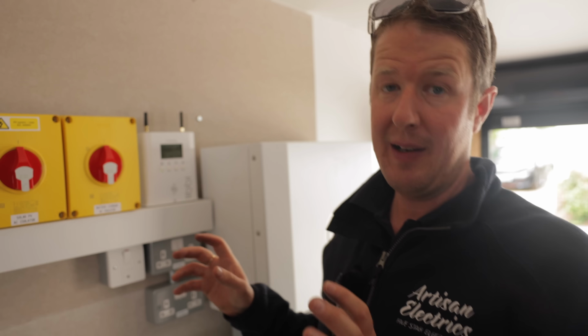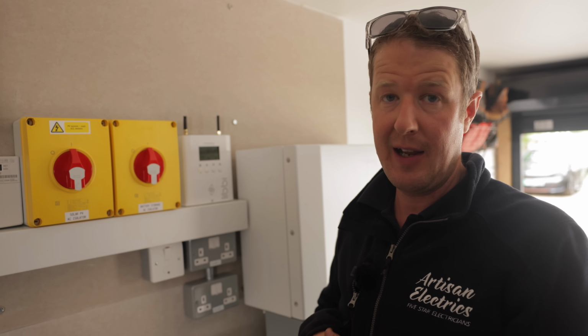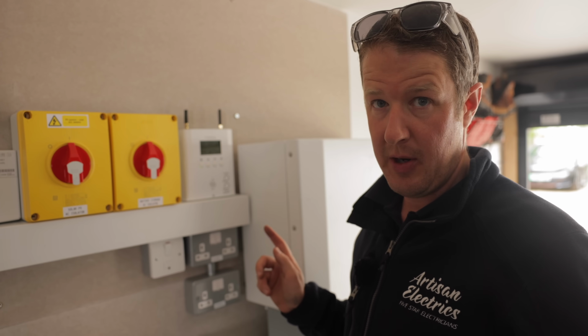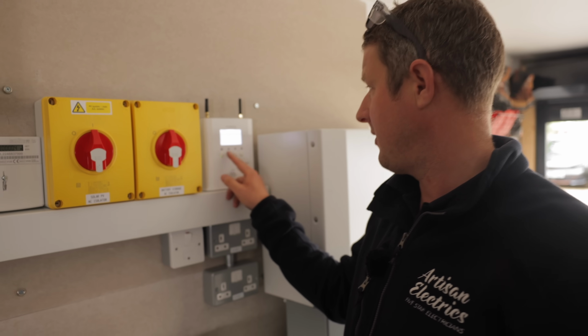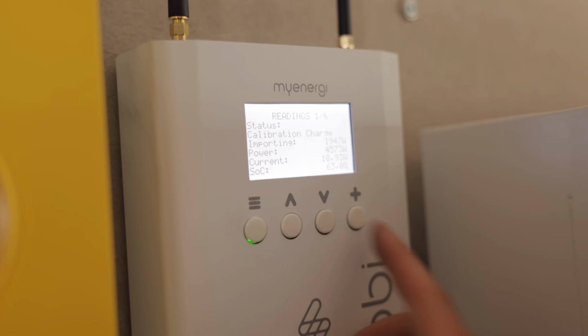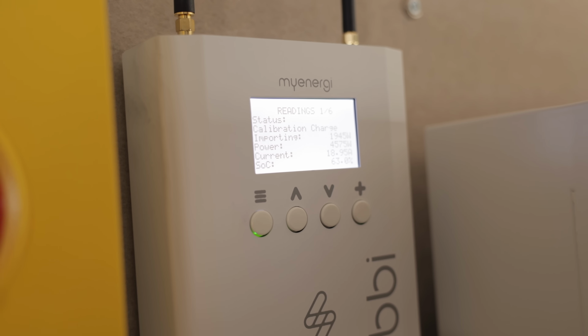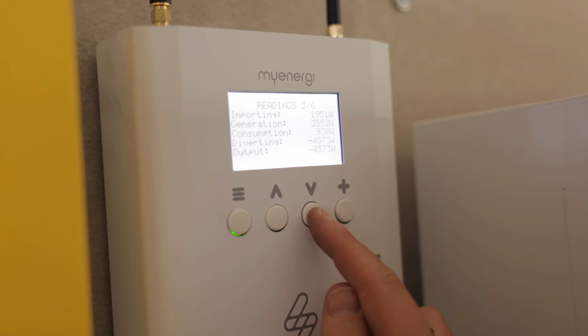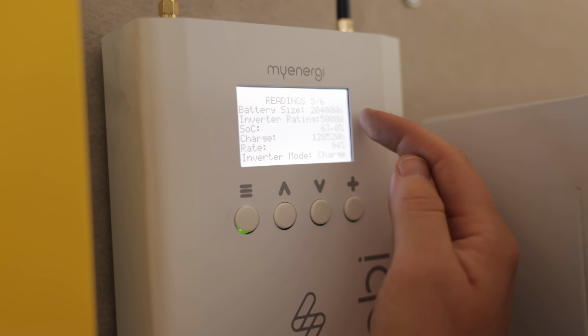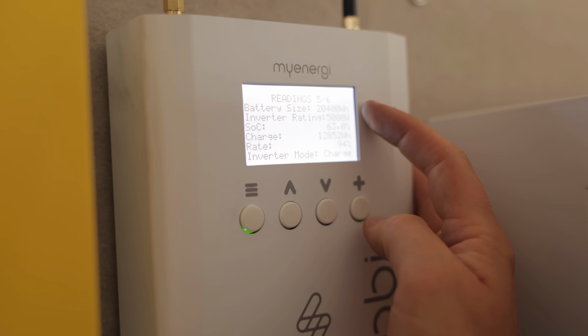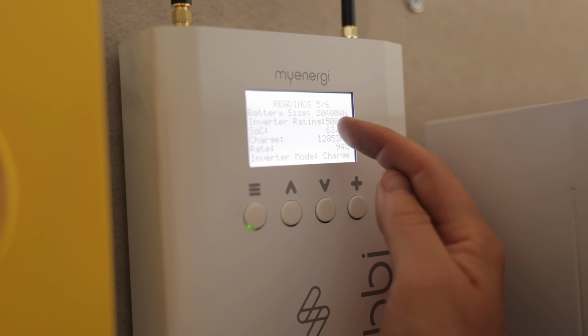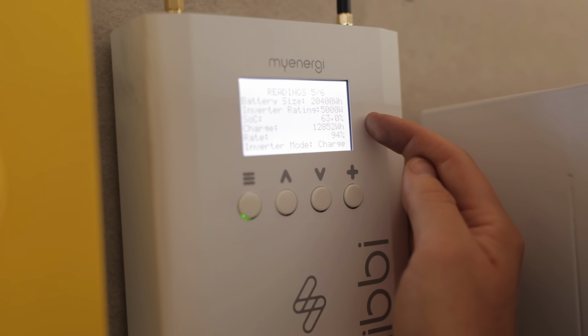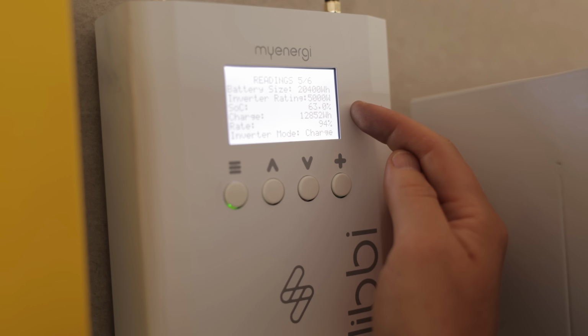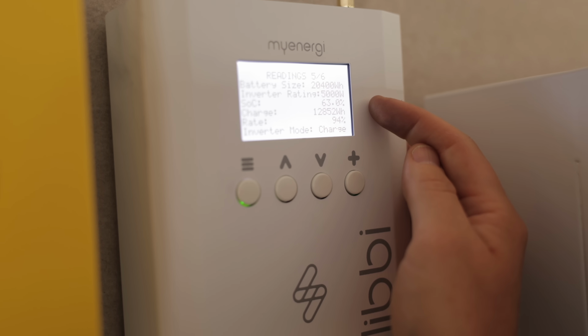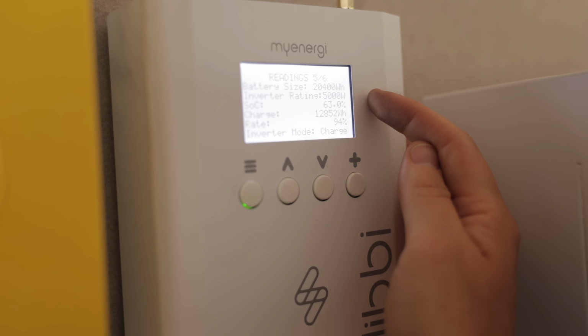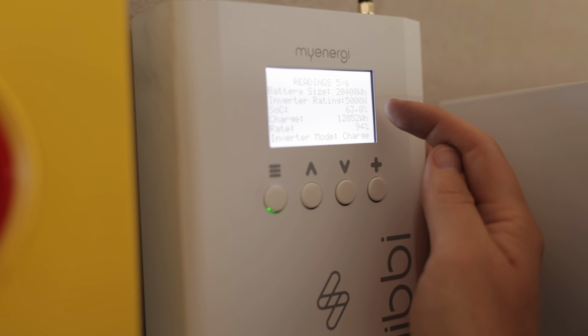Part of the setup is what's called commissioning, which is in the installation guide. You need to check that all the batteries are communicating with each other. To do that, go to main menu, readings, then page 5 of 6, and make sure the battery size matches the amount of batteries fitted. In this case, 20,400 watt hours, so 20 kilowatt hours, inverter rating 5,000 - that's correct. If the battery size isn't showing all the modules, maybe only 15 kilowatt hours, that means one of the modules isn't talking to the others, and we need to check the communication cables.